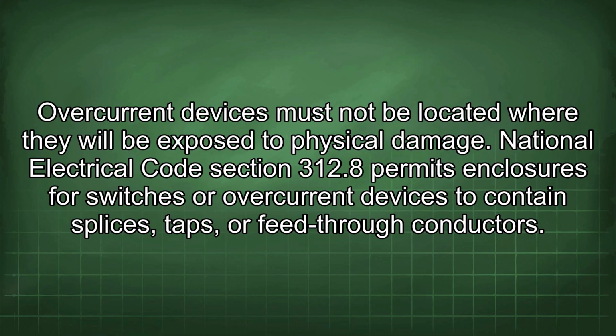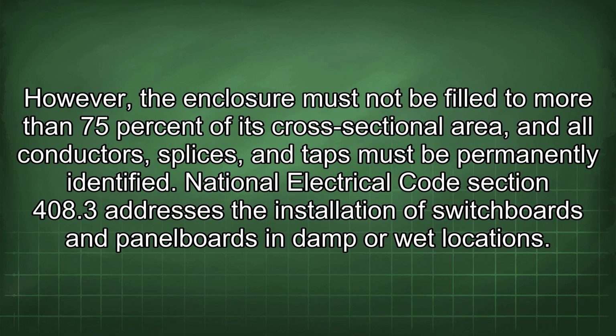National Electrical Code Section 312.8 permits enclosures for switches or overcurrent devices to contain splices, taps, or feed through conductors. However, the enclosure must not be filled to more than 75% of its cross-sectional area, and all conductors, splices, and taps must be permanently identified.